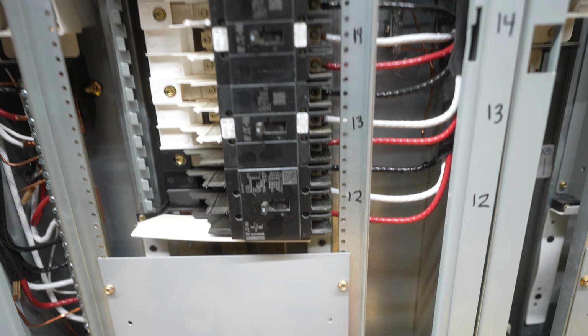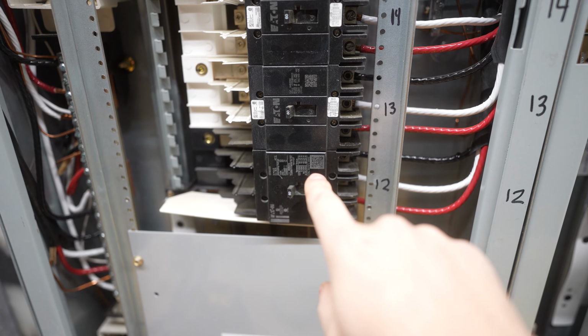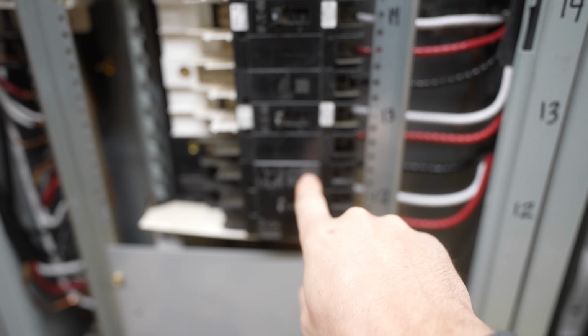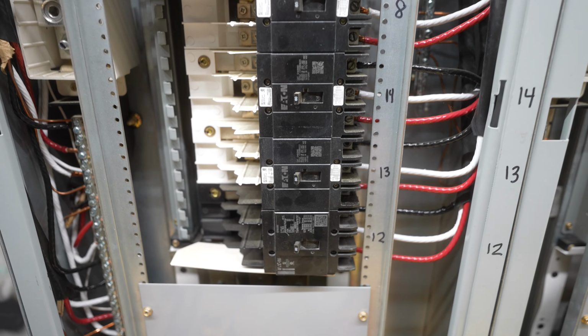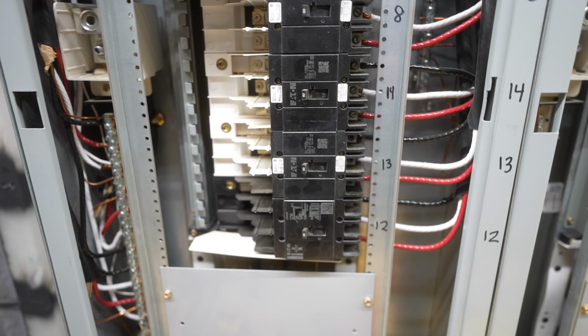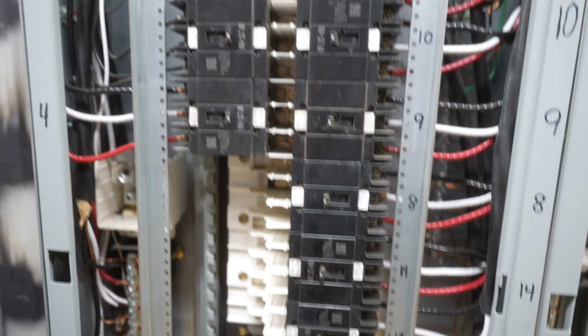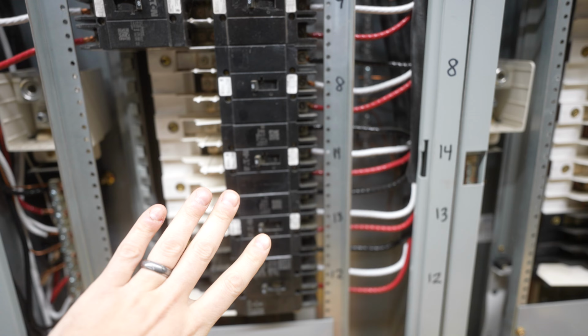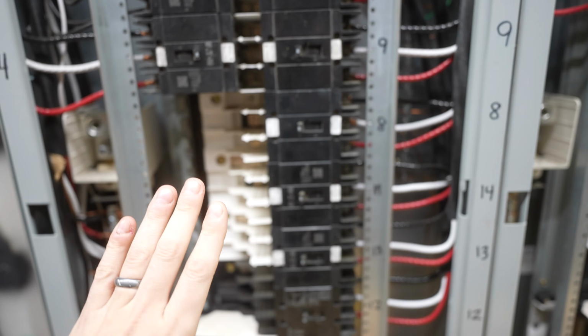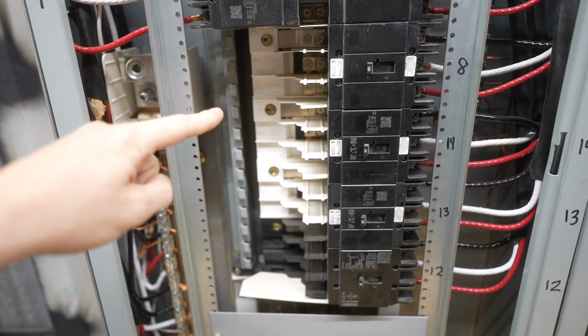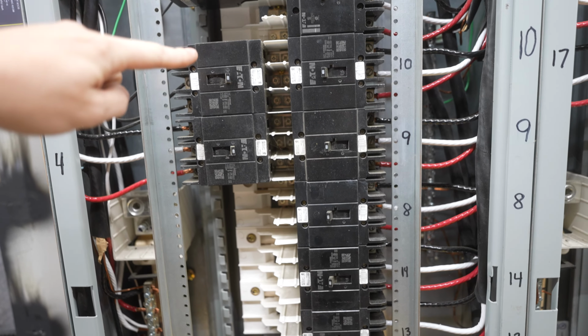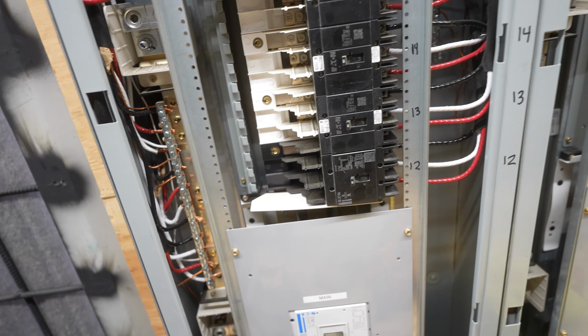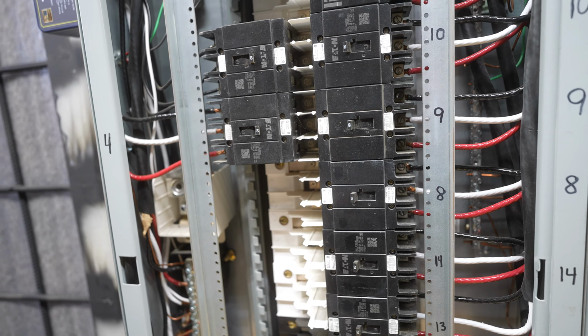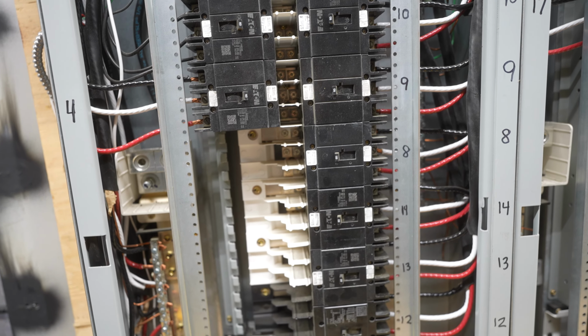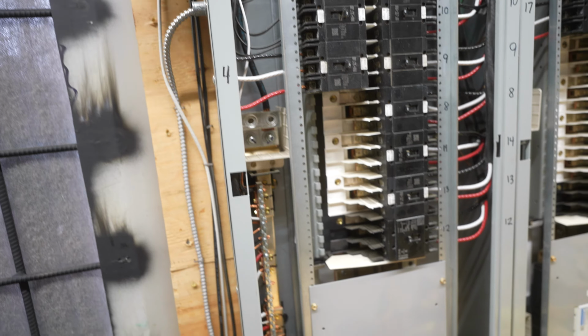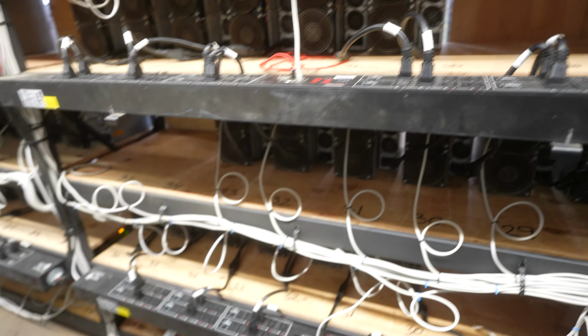This setup is a lot better because it requires less space, since each miner is fully on its own leg, not sharing with another. So you save on breakers and copper. You can see this panel is fully loaded, there are no more watts available, but you can see how much space we still have left over. That's because these are single legs being run on each, so the miners run on a single leg and you save a lot by doing that.